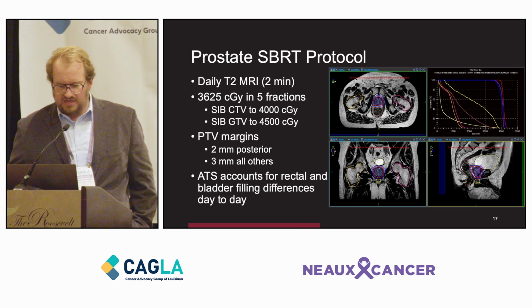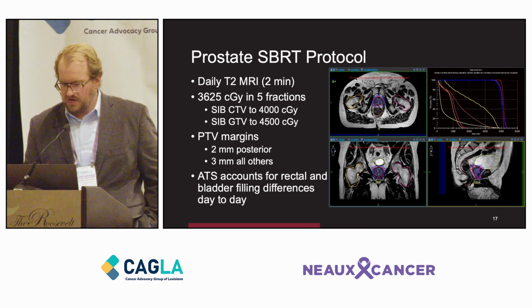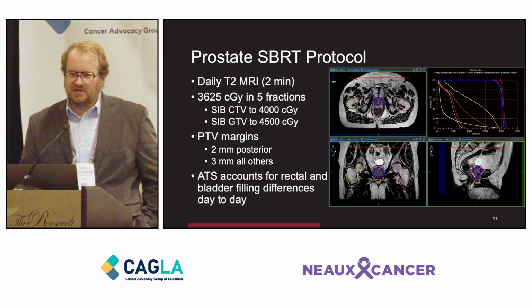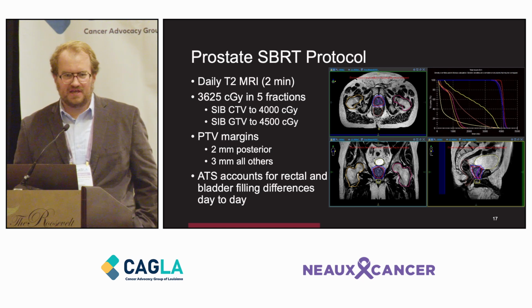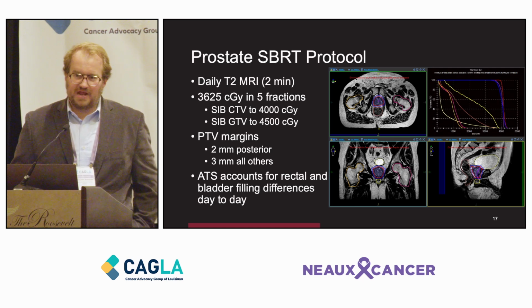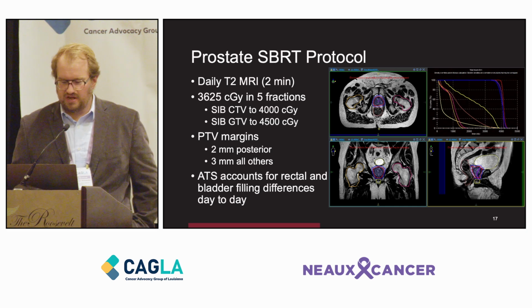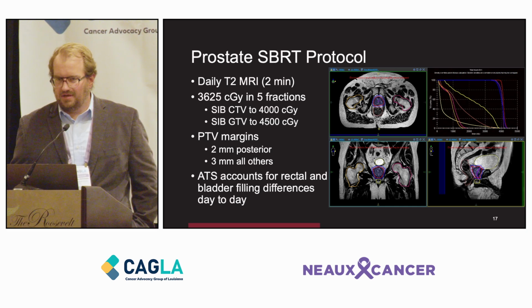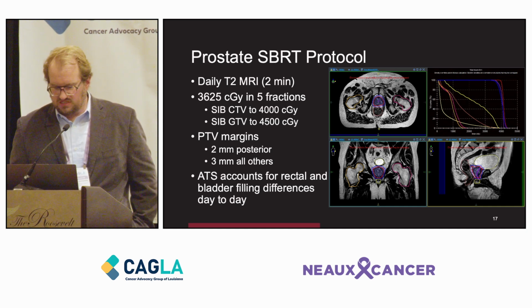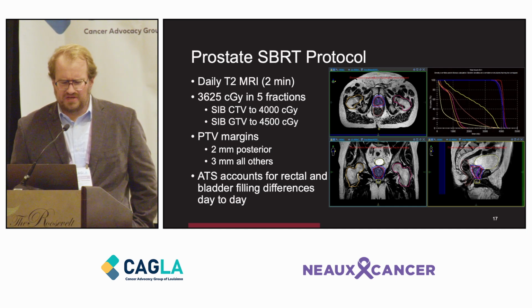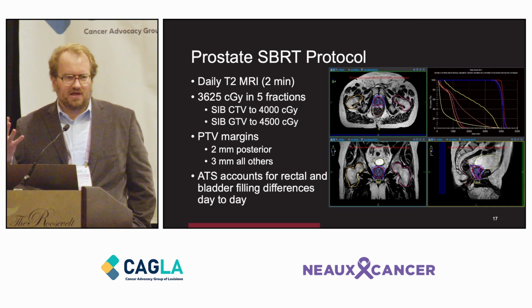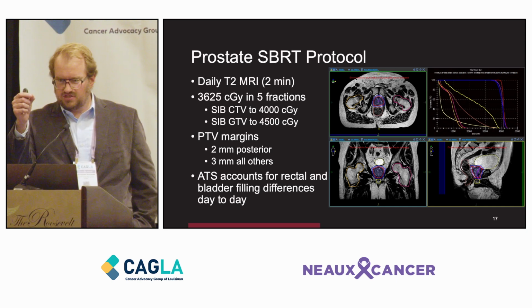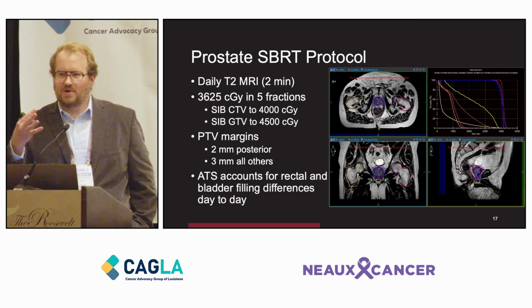What equipment do you need? In addition to the Elekta Unity, in order to test all of this, you need an MRI-compatible motion phantom, either an anthropomorphic one that mimics a patient and human anatomy, or something simpler. Sun Nuclear makes the Zeus phantom, and a company called Modus makes the QUASAR MRI 4D motion phantom, and they have an MRI-safe motor so that we can have a target that we can track, and it moves around inside this larger phantom.